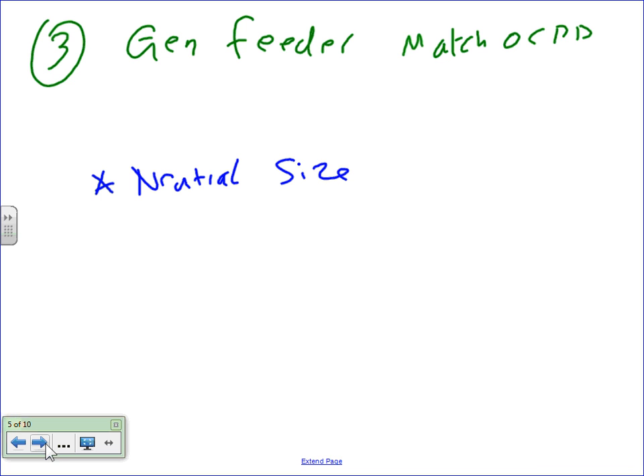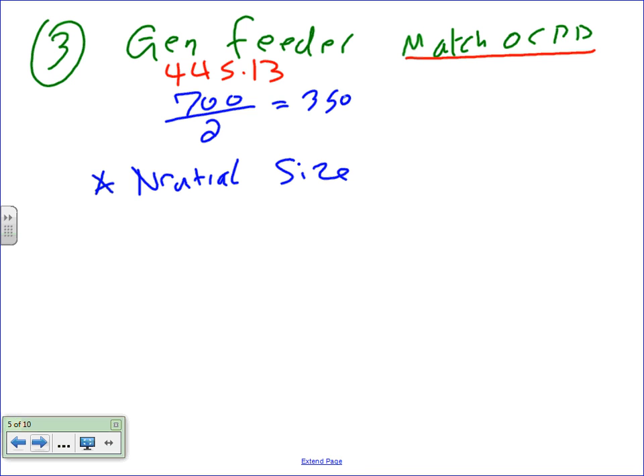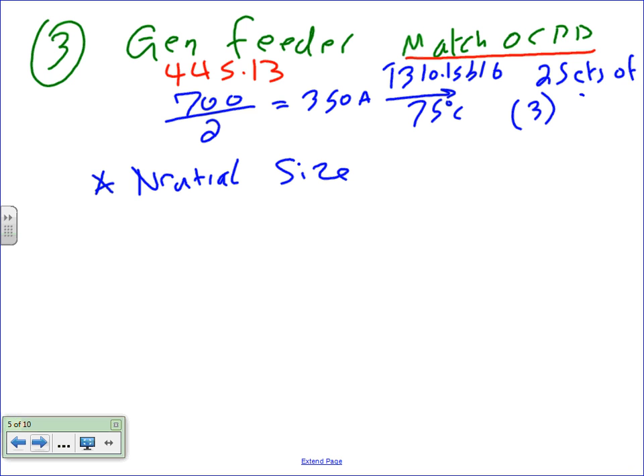The generator feeder size that you guys are going to be using, I said match the overcurrent device. Match the overcurrent device. And this is also from 445.13. Same calculation. Generator feeder size, match overcurrent device. So what was my overcurrent device size? I have a 700. I need to parallel here. Divided by 2, that will give me a healthy 350 amp. Take this one to table 310.15(B)(16) under the 75 degree column. That will give me a healthy 2 sets of 3 conductors. Each one of them is 500 kcmil, THHN, unless I know otherwise. THHN, could be THHW.